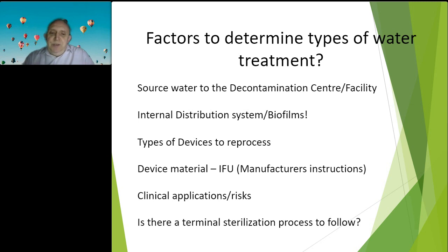Types of device we're using. What are the risks? Are we going into highly sterile areas of the body, or are we just piercing the outer membranes of the skin? Does that make a difference when it comes to water quality? And probably the most important factor is whether there's a terminal sterilization process to follow.